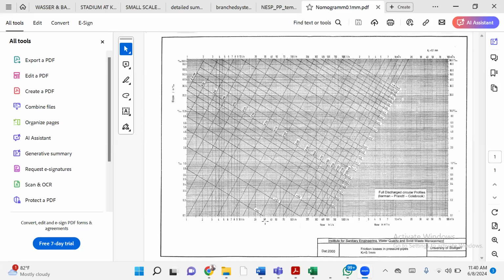Camping, for example: when you calculate the volume for the camping, you discover that you have less than the 40 mm diameter that is on the chart. I said anything that's less than 1 liter per second, you use the value for 1 liter per second. It means 40 mm is the minimum you can use.